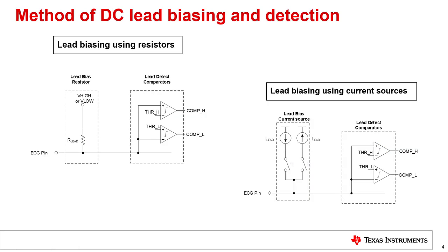Lead detection requires biasing the leads to a potential which could be high or low. Such biasing could be done either using a resistor or a current source. When a resistor is used for biasing, the other end of the resistor can be connected to a high-side potential, V-high, or a low-side potential, V-low. When the lead is open, the pin gets pulled by the resistor to V-high or V-low. When the current source is used for biasing, the polarity of the current source — either source or sink — determines in which direction the pin gets pulled when the lead is open.